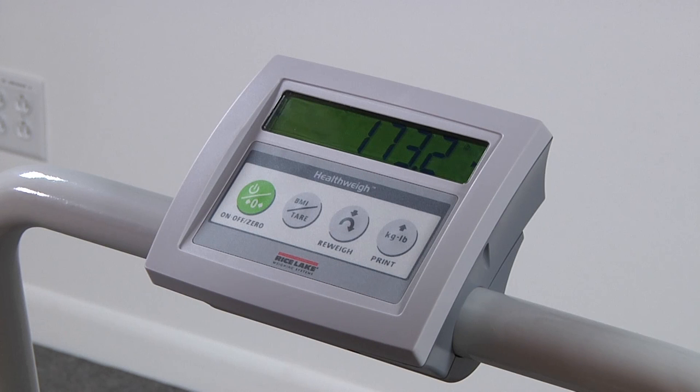Your scale comes with an internal BMI calculator for easily calculating a patient's body mass index. It's important to note that if calculating the BMI of a patient in a wheelchair, the TARE function must be engaged to subtract the wheelchair weight. Not doing so will result in an inaccurate BMI calculation.